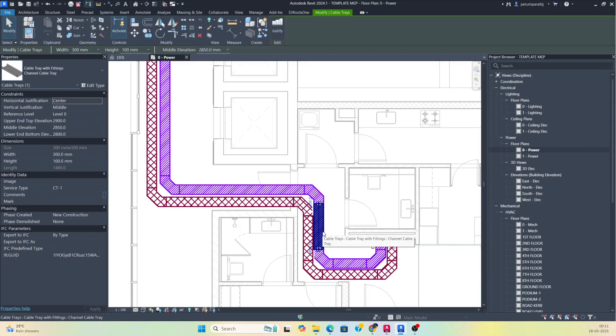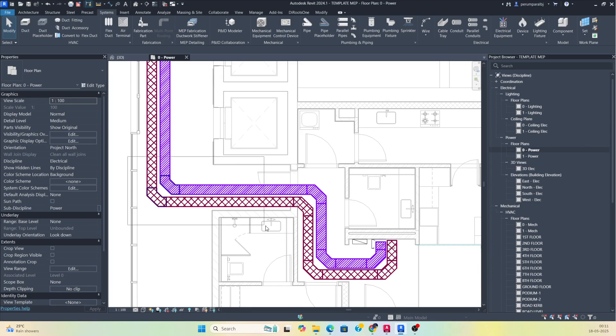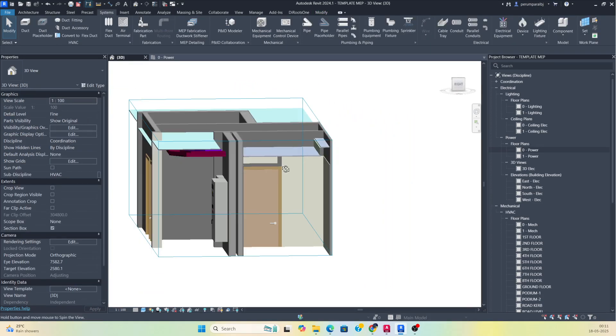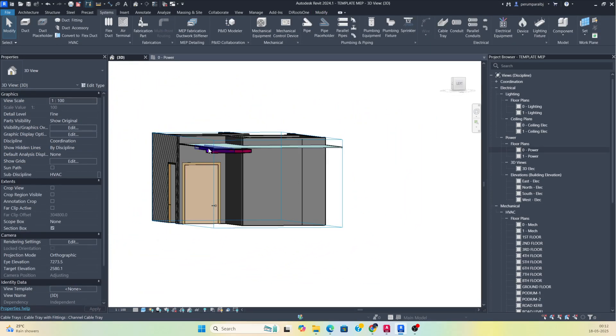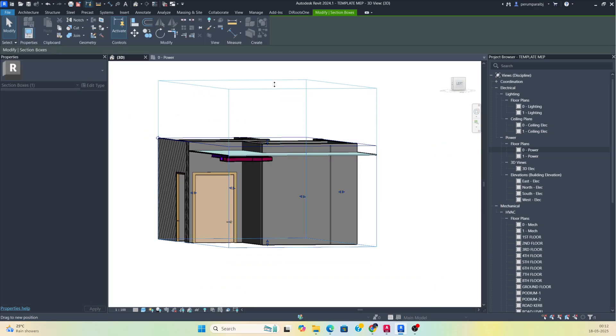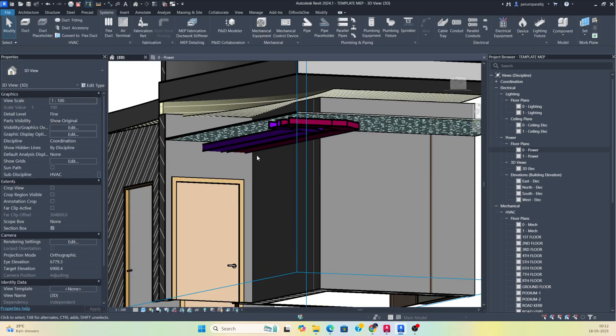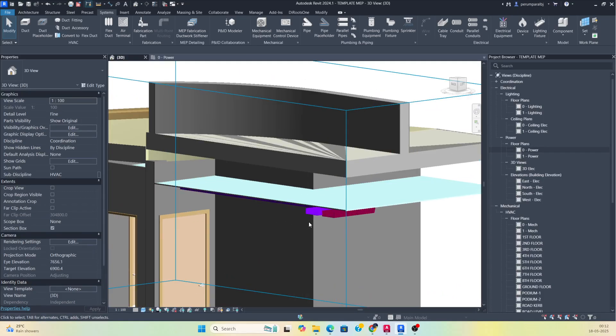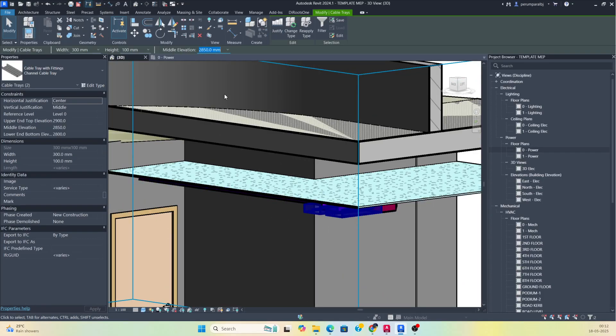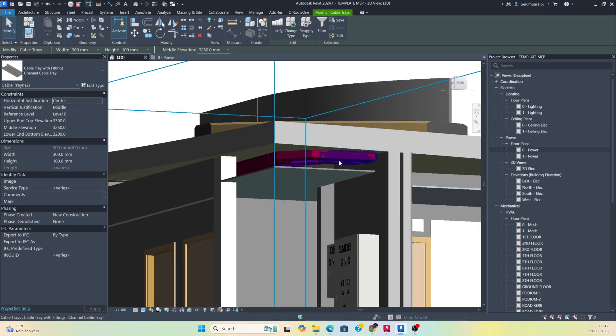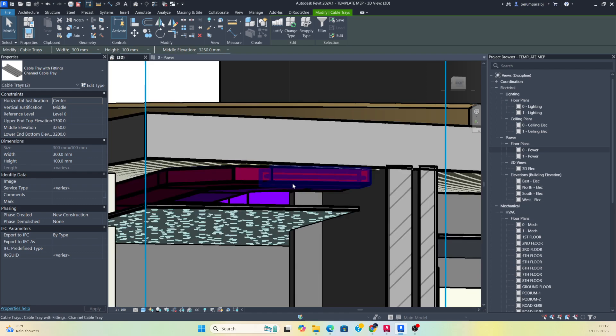If you look in the 3D view and try to select this one, you can see it is showing below the ceiling. So it was below the ceiling, and it's not possible to run below the ceiling. We need to run the cable tray above the ceiling. For that, you just need to change the elevation. I'm changing the elevation because our ceiling is here, so we need to change the elevation to about 3350. Now it is going above the ceiling.